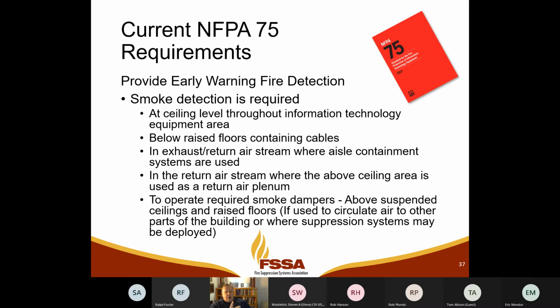And so what the code says is think about how the HVAC moves air in the space and put detection along that air path. And so in the exhaust or return air stream, as air has moved past the IT equipment, and that IT equipment may be having the fire, then somewhere downstream of that, that's where you put your smoke detection to try and capture smoke that may be coming from the IT equipment that we're trying to protect. Okay, does that make sense?